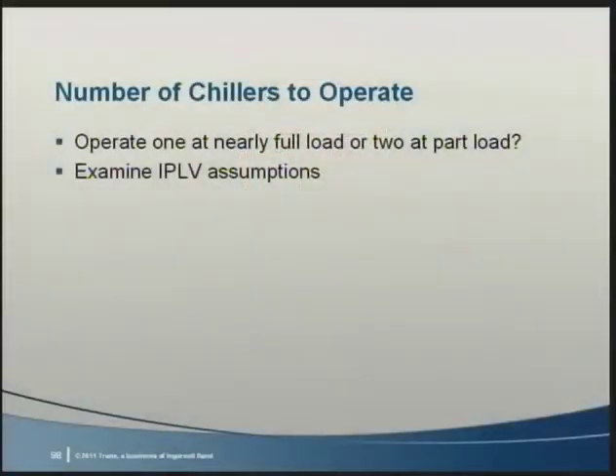As I said in the beginning, watch for rogue zones so that they don't defeat this control. On to the next topic. It's a question that seems to come up quite often today. Should I operate 1 chiller at nearly full load or 2 at part load conditions? To begin the discussion, we'll only look at chiller performance. We'll then expand it to include ancillary energy.